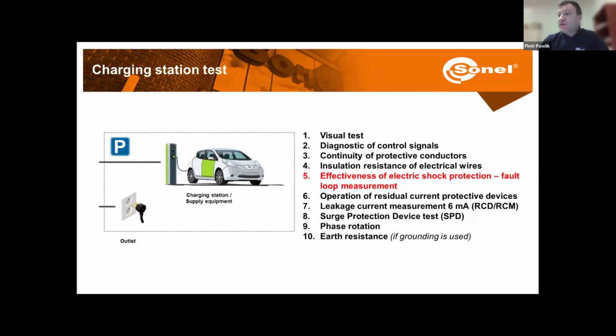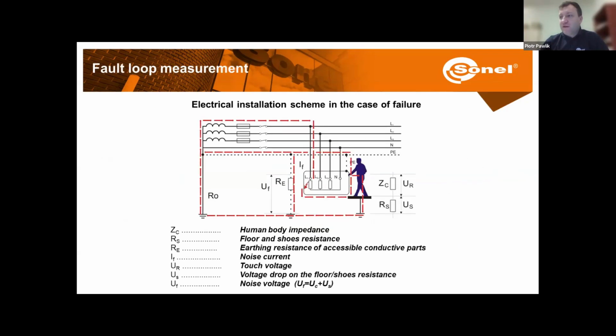Then the next thing that we need to check is the effectiveness of electric shock protection. So if our overcurrent breakers are working, and for that reason, we are going to check fault loop impedance. So how does it work? When we have a fault somewhere in the circuit, then we are going to have some potential on the cover. And we are going to get rid of this potential through the PE channel, so either directly to the transformer or through the ground, or through a body of some poor guy that is touching the cover of this charging station or other accessible conductive elements on the cover.